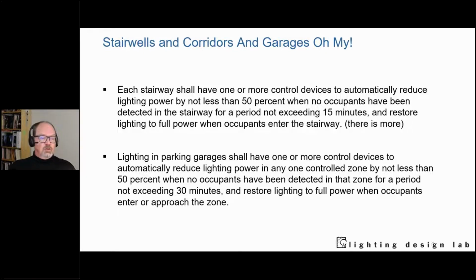Dim down to, say, 20% or in some cases 50% light output. The idea is you don't want to turn the lights off completely. You don't want people going into dark spaces and feeling scared, because then they won't like the lighting controls, and they'll figure out a way to disable them. It's better to harvest 80% of the power and dim up from there than to harvest 100% for a month until somebody disables the lighting control system. I hope that makes sense.